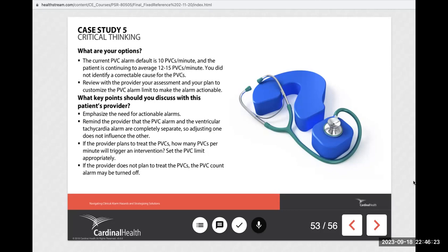Emphasize the need for actionable alarms. Remind the provider that the PVC alarm and the ventricular tachycardia alarm are completely separate, so adjusting one does not influence the other. If the provider plans to treat the PVCs, how many PVCs per minute will trigger an intervention? Set the PVC limit appropriately. If the provider does not plan to treat the PVCs, the PVC count alarm may be turned off.